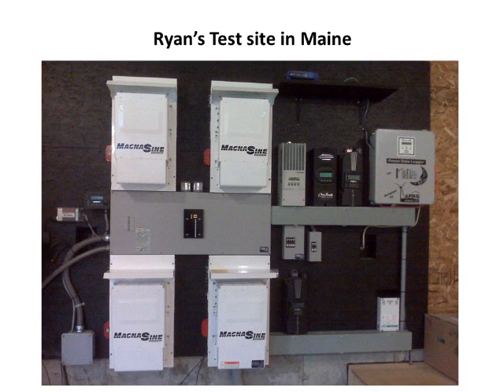The Classic would routinely harvest more kilowatt hours per day than the competition. Some were a lot less productive than others, and there were a couple real eye-openers. We always knew the MX60 was good, but we were surprised to find it outperformed the FM60 daily. We used to get beat up a lot over the MX60 and now the FM60, reading higher on the display for output than it really was. And not wanting to make that mistake again, we installed shunts internally on the input and output of the Classic so the display is highly accurate.